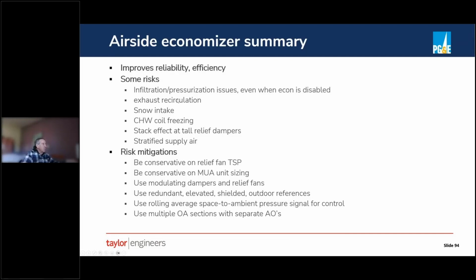Exhaust recirculation, we talked about that with the package units. It can be a tricky thing. With data centers, you're bringing massive, massive amounts of air, and configuring your intakes and exhausts to keep them from recirculating is non-trivial. Certainly can be done, but as the data centers get bigger and bigger, it gets harder sometimes. Snow intake. Data centers are going to be in places where it snows, and we've seen real issues with snow being sucked into the outside air intakes and then basically becoming water in your system, right? Getting your filters wet, sucking through your mechanical system. Coil freezing, you need freeze protection. You need to think about how you're going to avoid that.